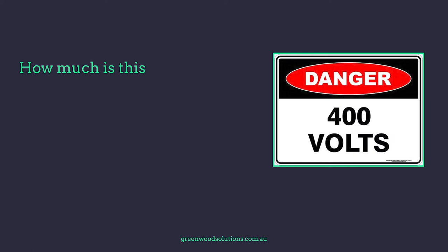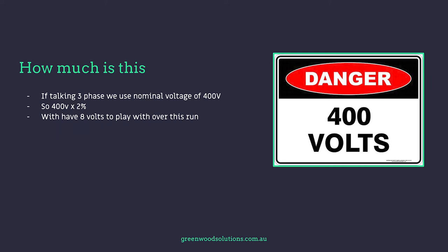So how much is this volt rise? Effectively we're talking about 400 volts with three phase — so that's 400 volts times two percent. We have eight volts to play with over the whole run.